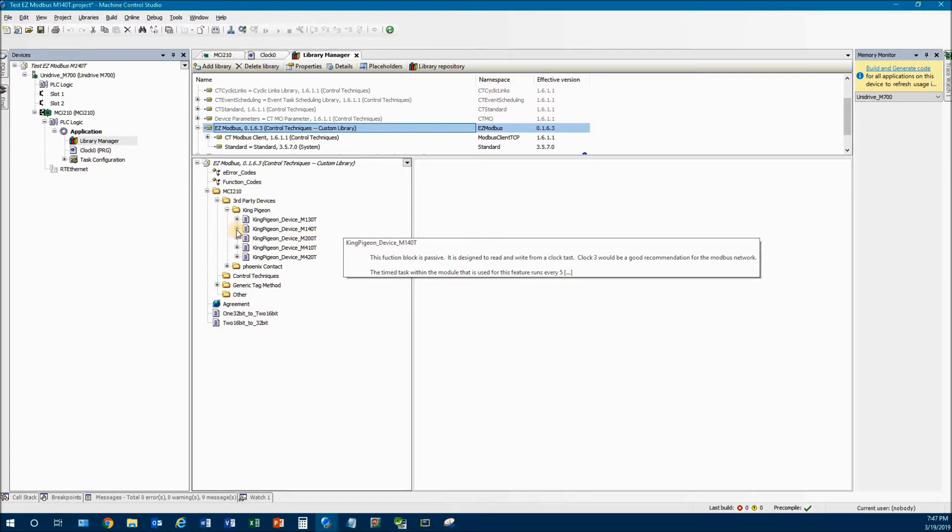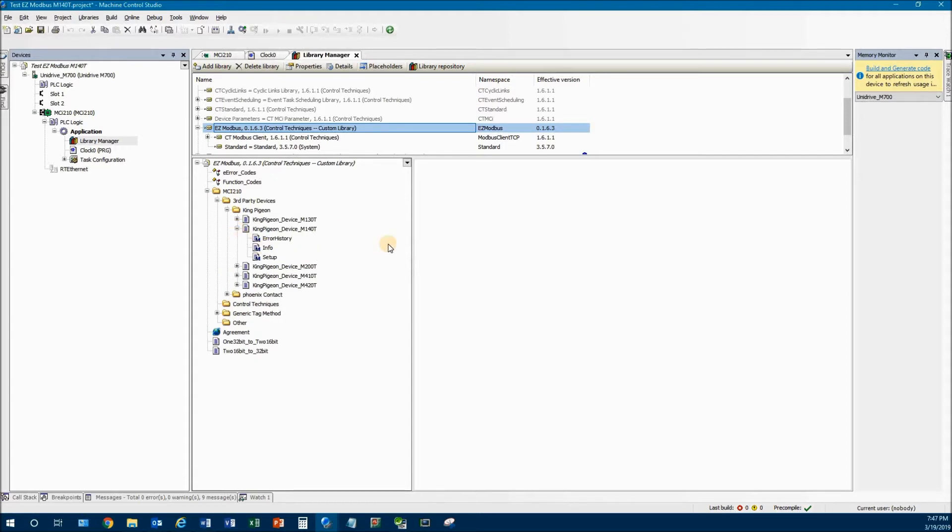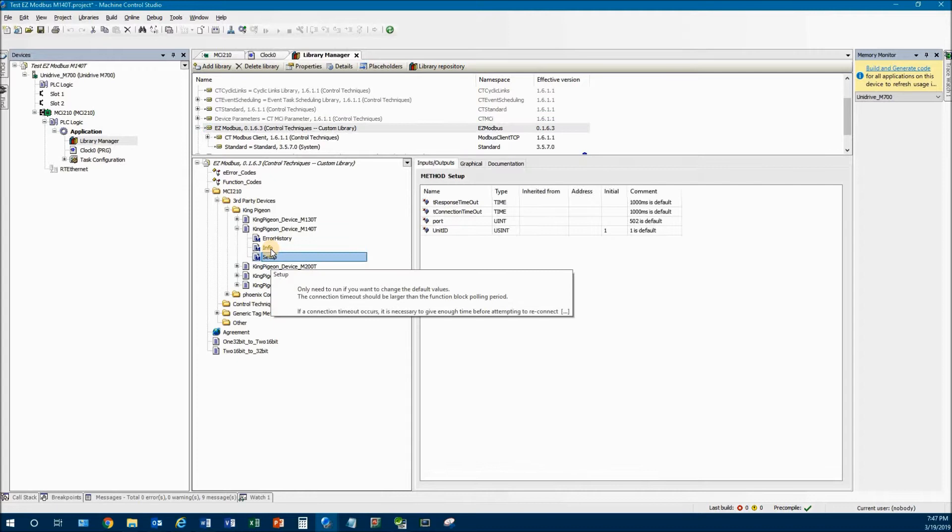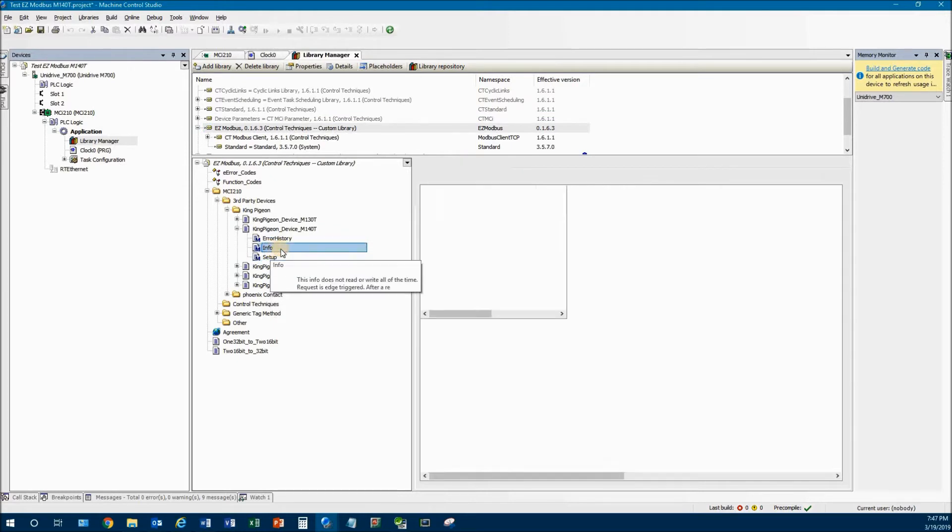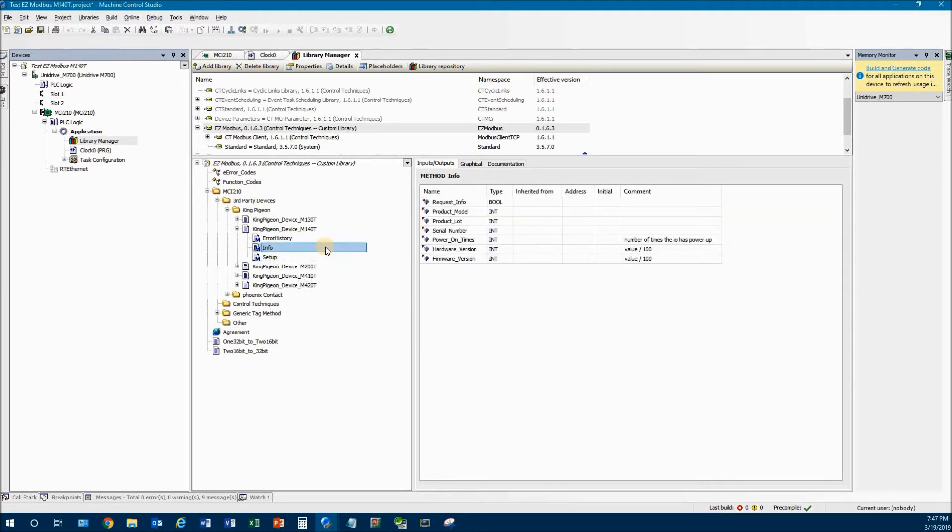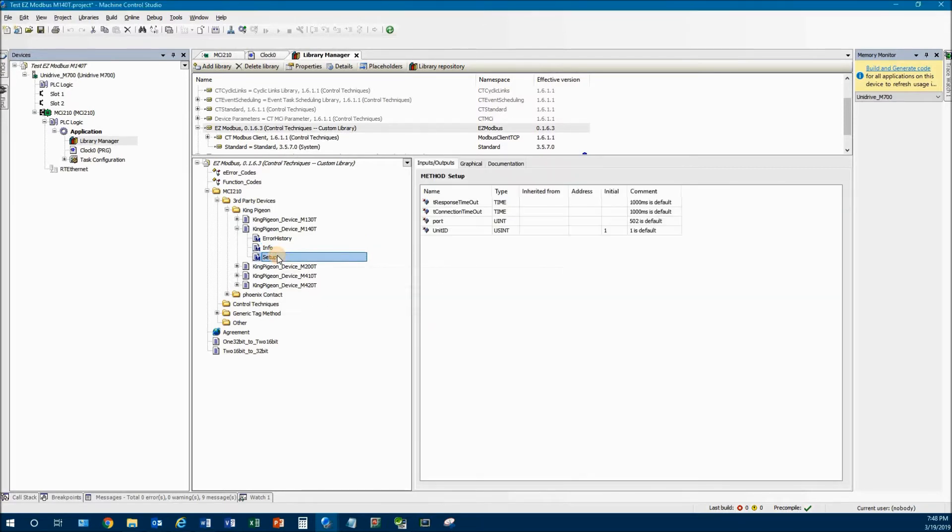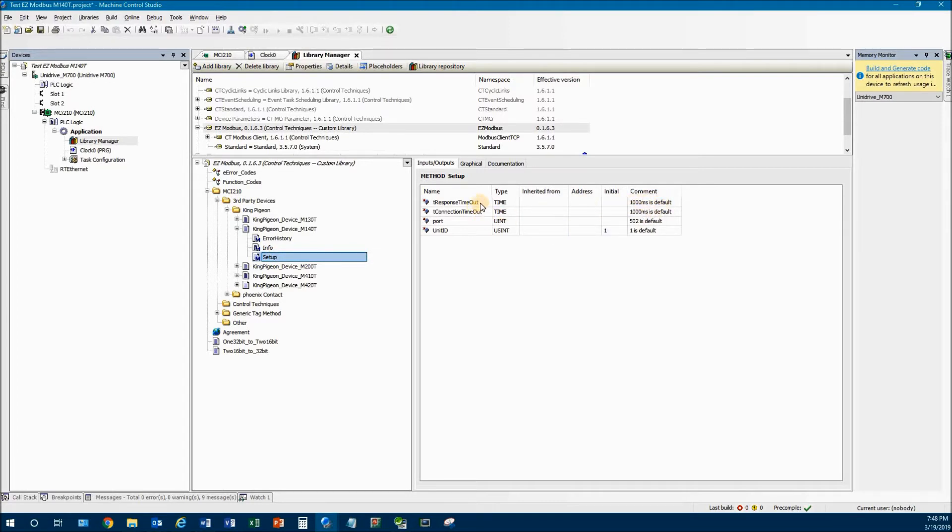And you can see that there are three blocks underneath it. Most of the time, you will not need the setup or the info. The info block is specific for the King Pigeon device. It really just reports back a serial number, the number of times it was powered on, some hardware version information. The setup, this is for alternate setup for the Modbus timeouts and port numbers. As you can see, by clicking on it, there are some default settings here. So the timeout for the response and the connection are both set to about a second. The port's default is 502 and the unit ID is 1.